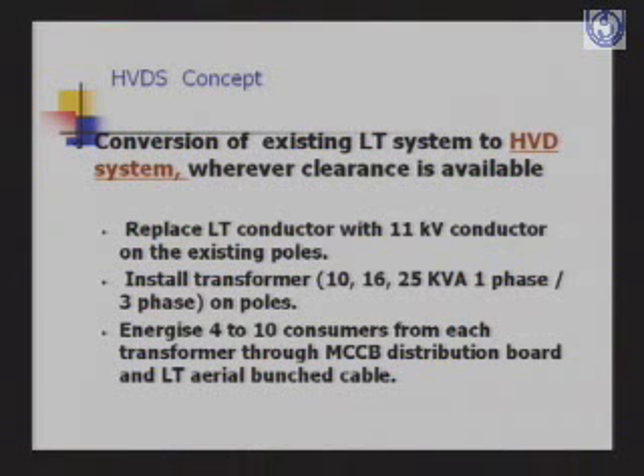Conversion of the existing LT system to a high voltage distribution system can be done wherever clearance is available. That is very important. Wherever clearance is available, replace the LT conductor with 11 kV conductor on the existing poles, install small capacity distribution transformers and energize 4 to 10 consumers from each transformer. If clearance is not available, then you will have to install either risers on the pole or replace the pole. If the pole height is much less, you can increase the height of the pole by putting a riser on the pole.